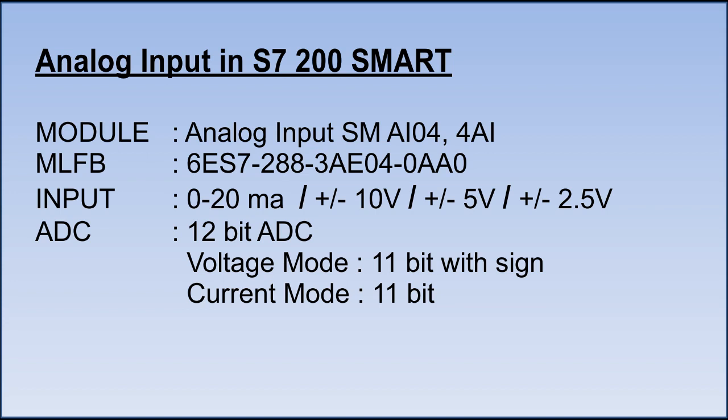In my configuration, I have used SM AI04 module. This module can accept 0 to 20 milliamps current or plus or minus 10 volts or 5 volts or 2.5 volts DC. This module has 12 bit of resolution, 11 bit of resolution is for measurement and 1 bit is for sign in case of voltage mode.